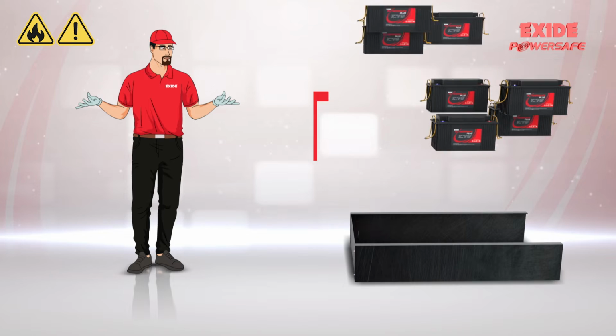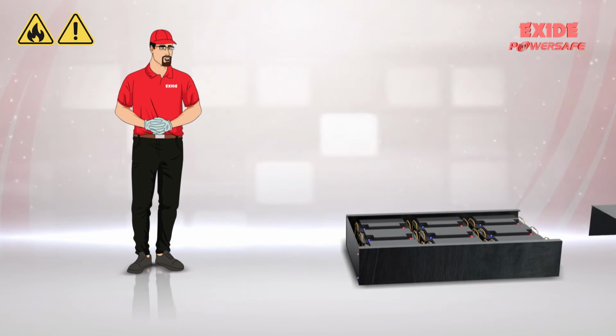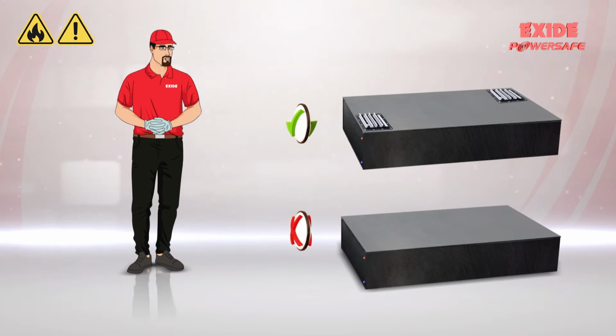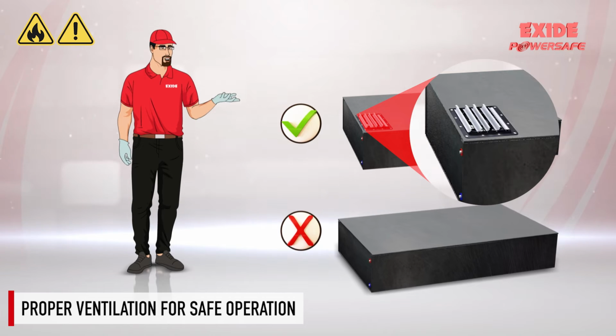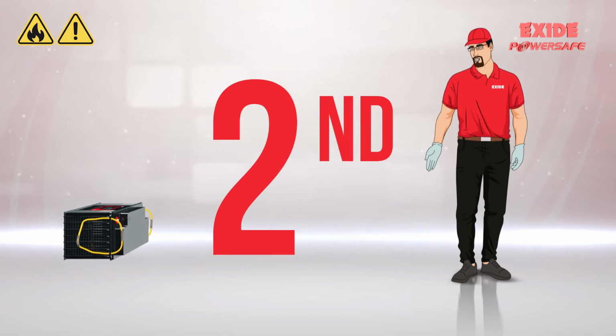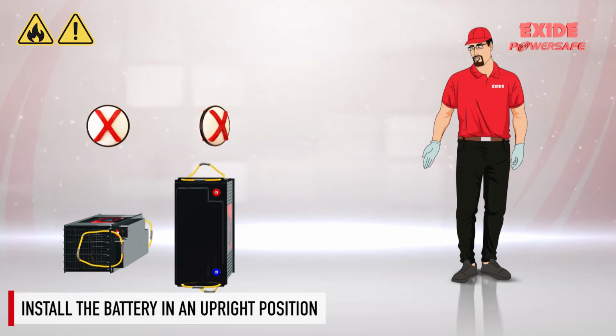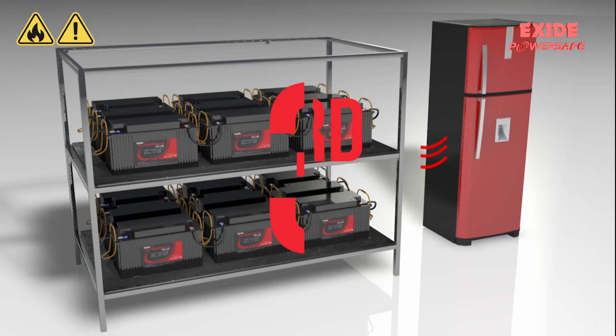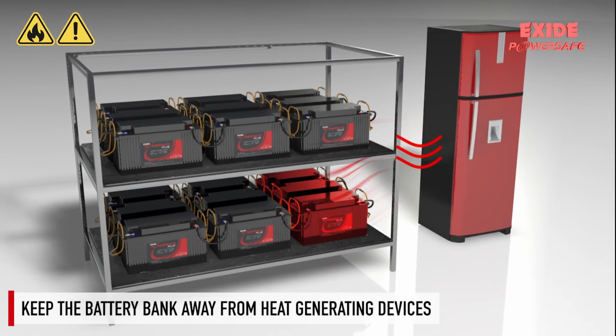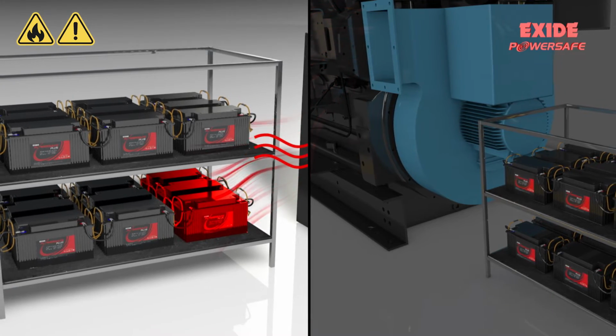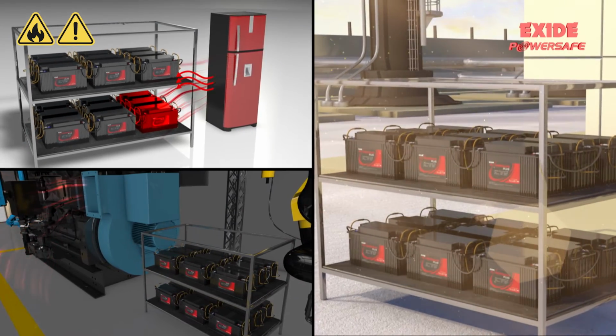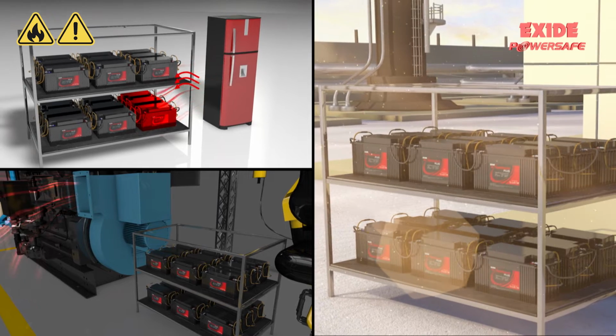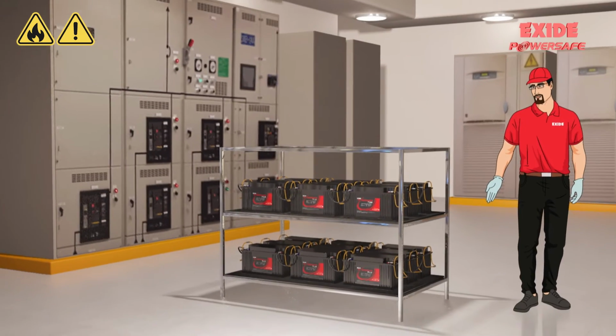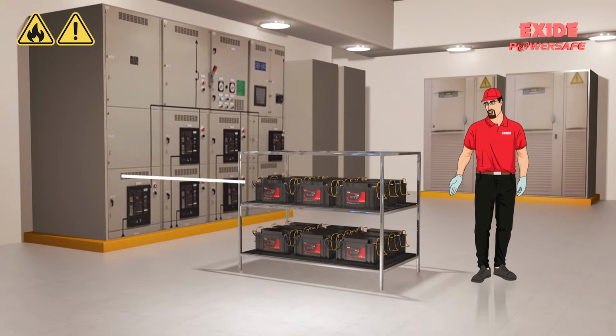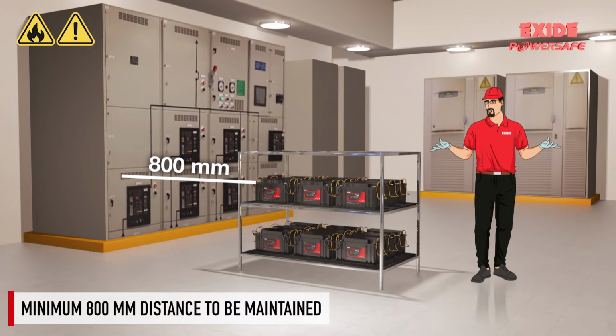First, your VRLA battery bank should not be put in any hermetically sealed vessel or cabinet. One must ensure proper ventilation for the safe operation of the batteries. Second, your VRLA batteries must be installed in an upright position. Third, the battery bank must be kept far away from any heat-generating device such as AC compressors, blower fans, refrigerators or from direct sunlight. Fourth, the battery bank must be kept far away from any electrical or electronic component, and the separation distance must be at least 800 millimeters.